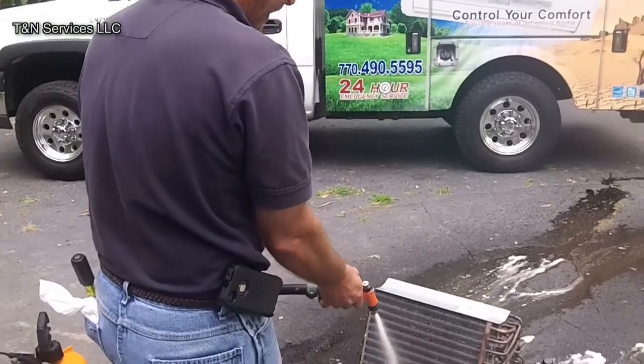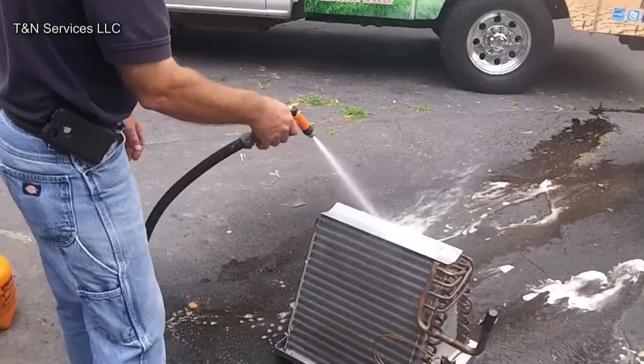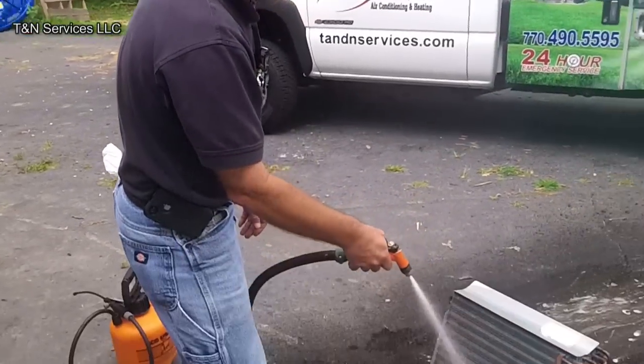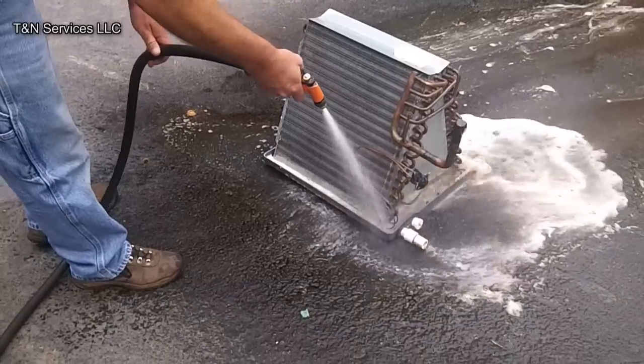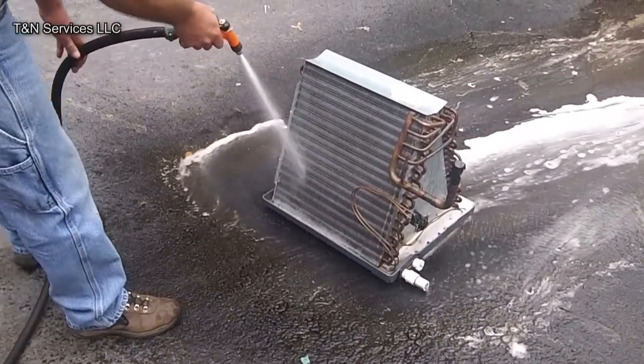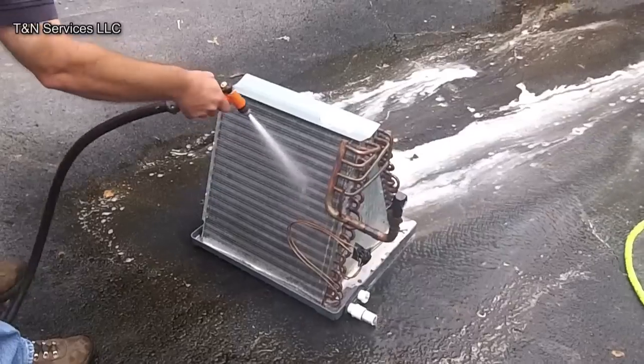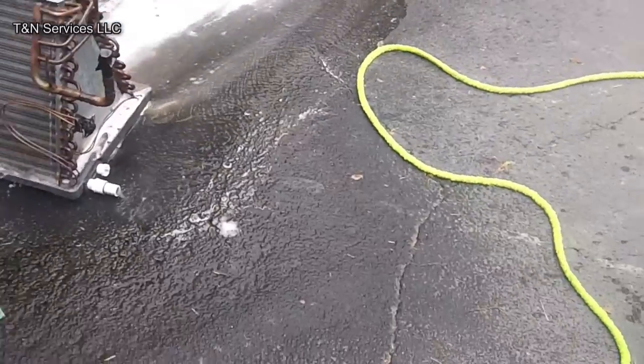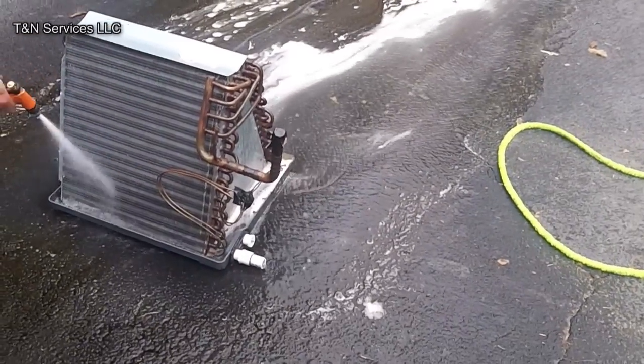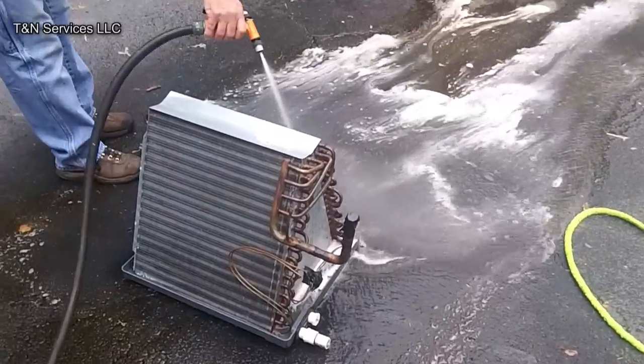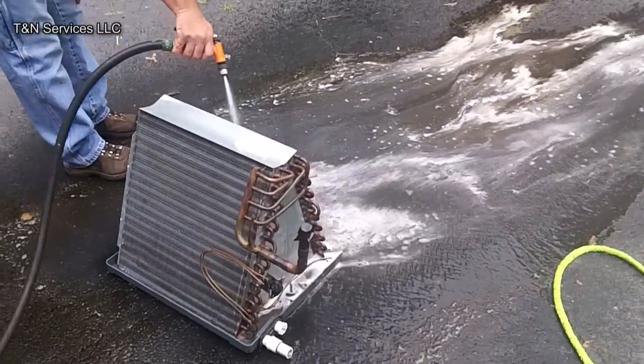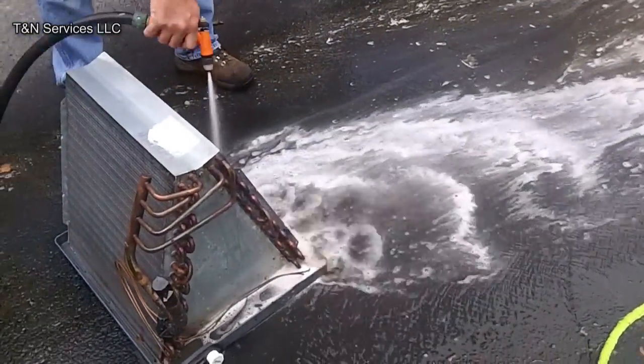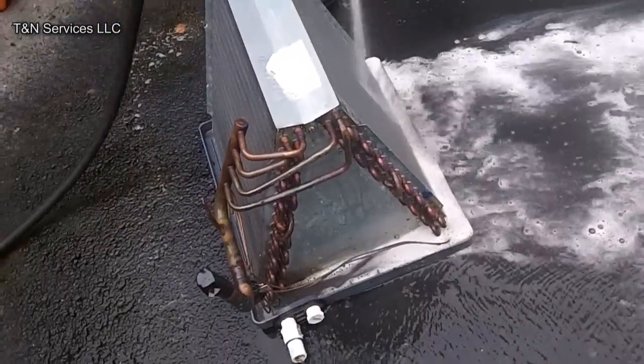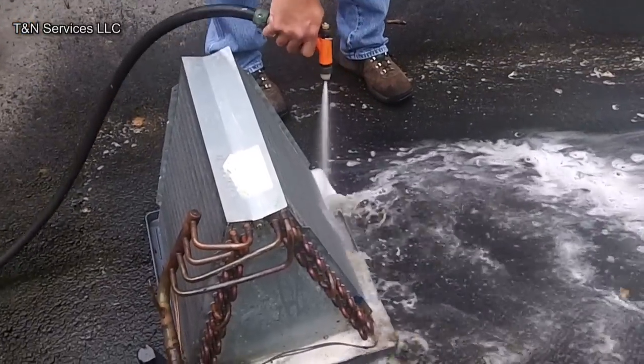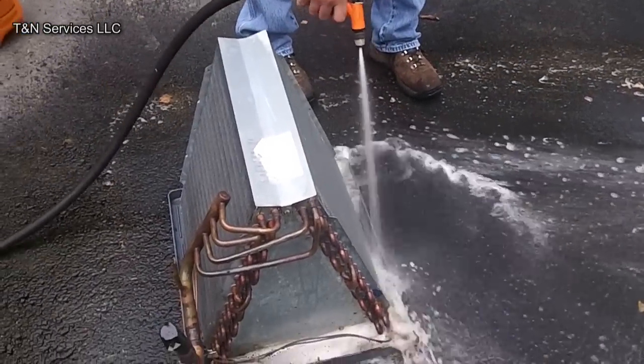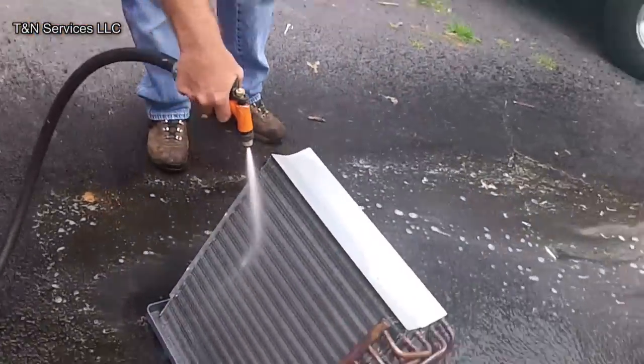Alright, now we got it sprayed down with coil cleaner. We may wind up having to give it a second shot because it is pretty dirty. Clean the drain pan, but this is how you clean it. You'll notice I got my ends taped up because I don't want any water in the system at all. So we'll start on this side, and once we get the outside clean, we'll blow as much as we can back to the inside, then flip it over and blow out the inside. We'll probably have to wash this thing 2 or 3 times to get it really clean.